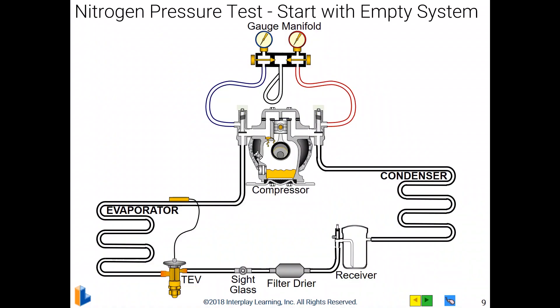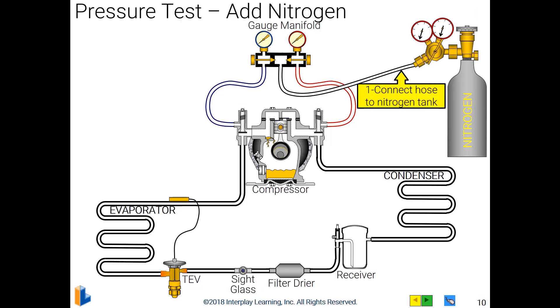Here's a diagram of a refrigeration system. We've looked at just about all these different components except for the sight glass at the bottom — we haven't talked about that yet. We have our gauges hooked up with the red hose going to the high side and the blue hose going to the low side. This is a three-port manifold with an extra hose in the middle — that's our charging hose. We have a nitrogen cylinder with a regulator on it, and we connect our charging hose, typically a yellow hose, to that regulator.